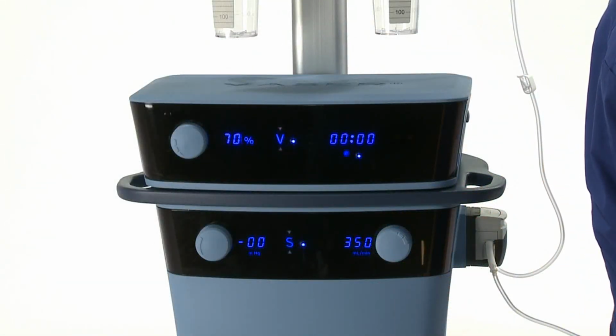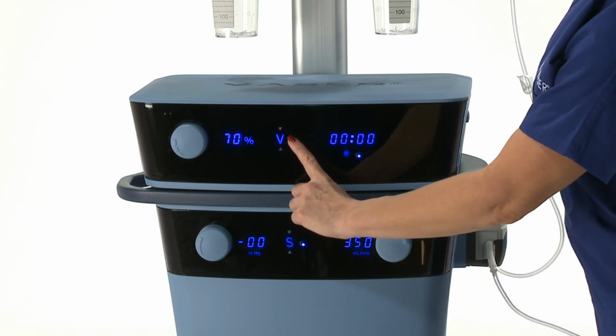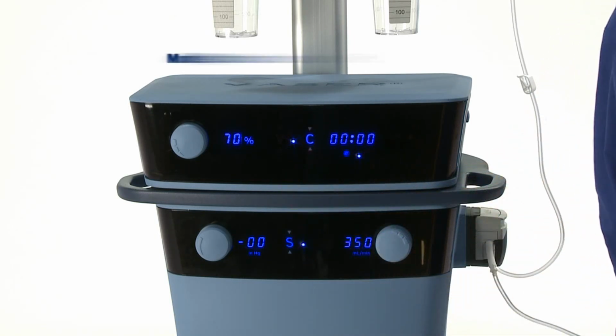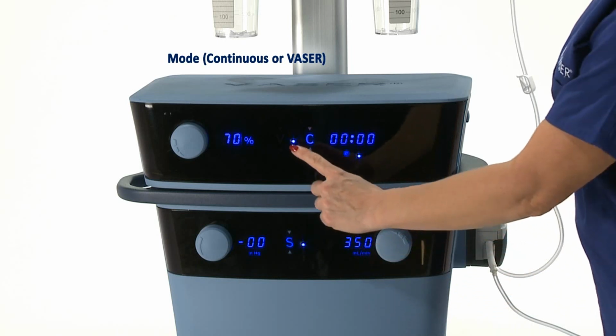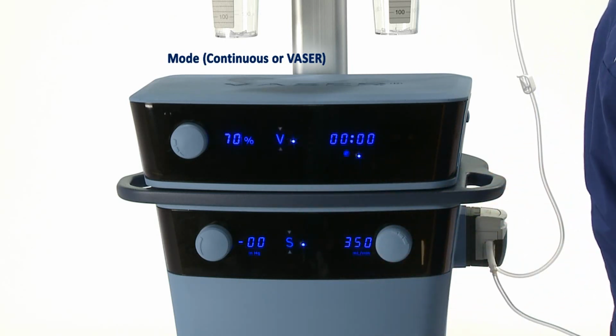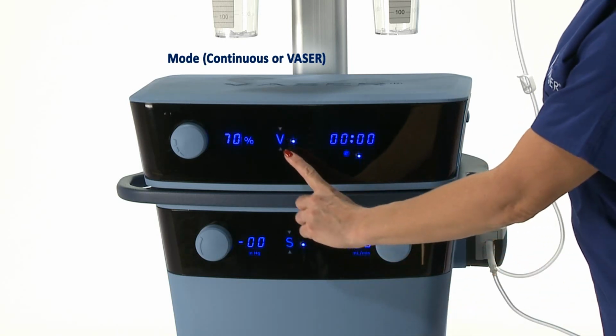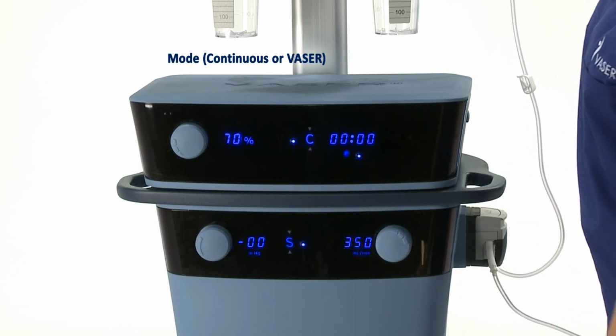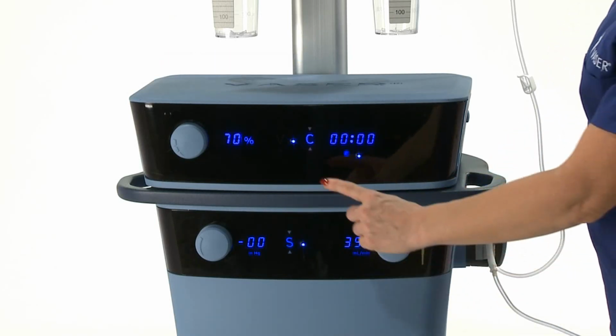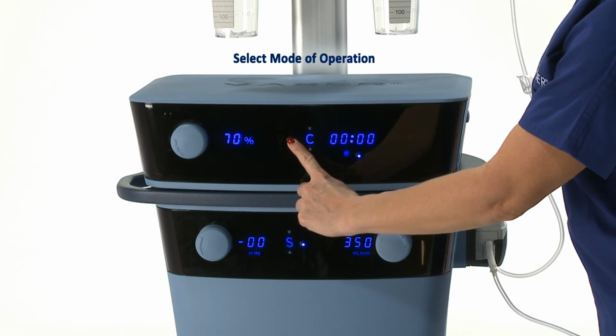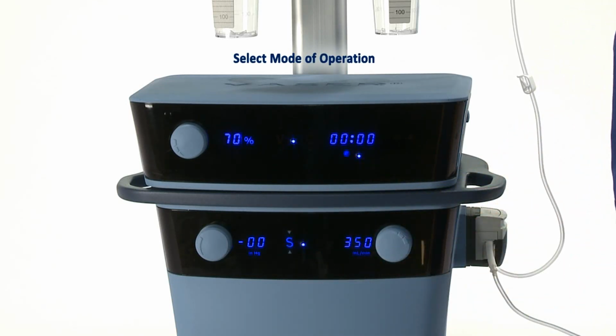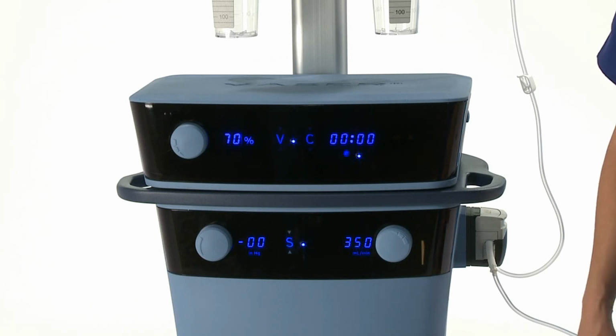During the procedure, the physician may request several adjustments to the Vaser amplifier. At the physician's request, toggle between continuous mode and pulsed mode, also known as Vaser mode. When not in use, the Vaser amplifier should be placed on standby mode for prevention of accidental activation. To initiate standby mode, press and hold the mode selection button for 3 seconds. Standby mode is indicated by a flashing V and C on the display panel.